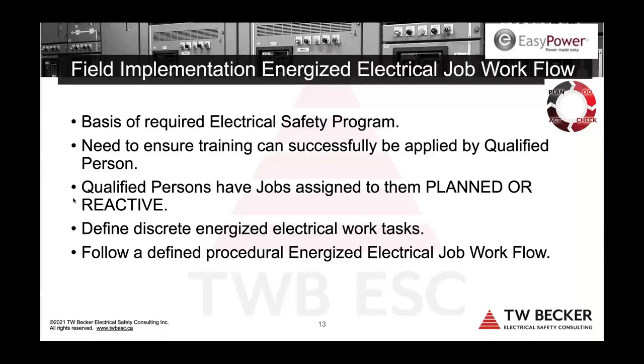So field implementation, this energized job workflow. In my opinion, and this is how I frame it, this is how the electrical safety program should operate: around the fact that we've got to have this management system, appendices, forms, flowcharts, and infographics that are delivered to the qualified person so they can implement this job workflow in the field. And as I said, be very successful in either eliminating or reducing their personal risk to as low as reasonably practicable.